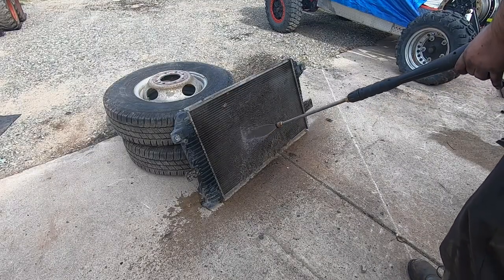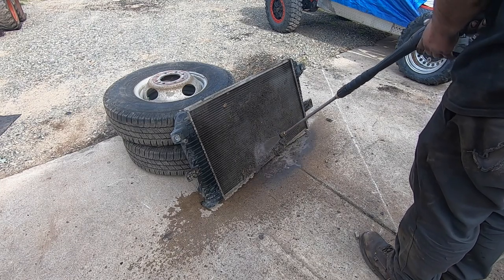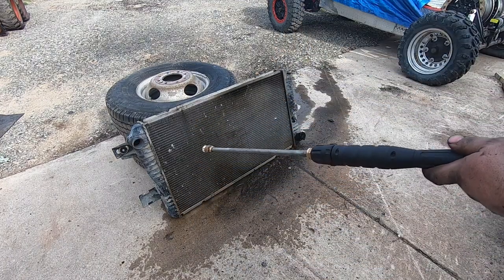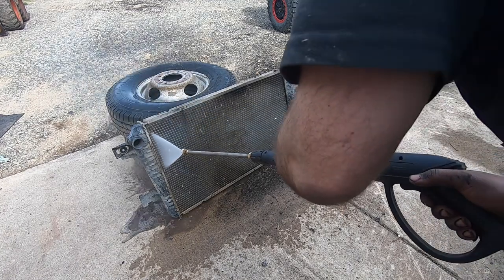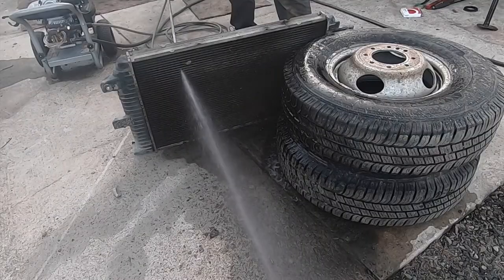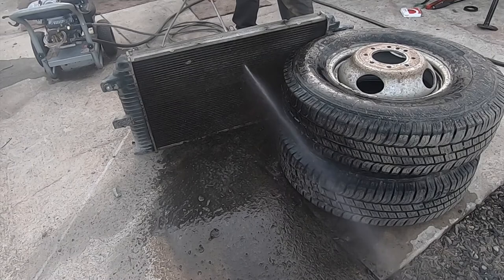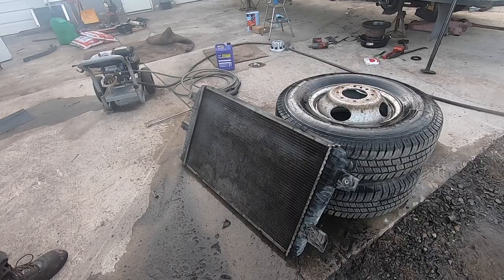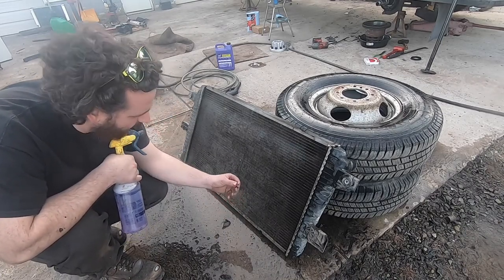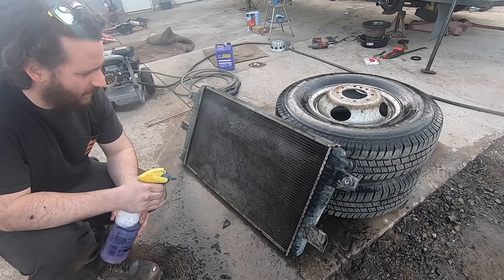Let's clean this out. This is a pretty gentle nozzle — you want it to stay perpendicular with the fins. Water passes through it now, but it's still just crudded up with crap. This is really worse than I was expecting. I'm going to hit it with some Purple Power and just let it soak, hopefully start softening up some of the buildup, and then we'll blast it again.